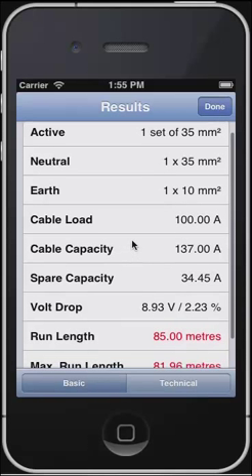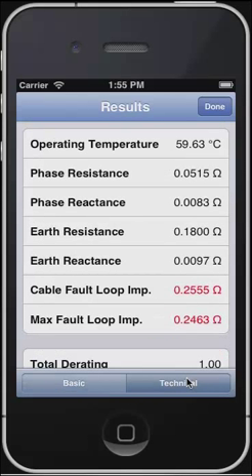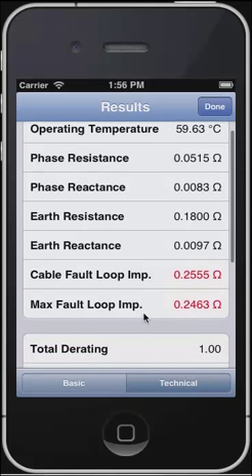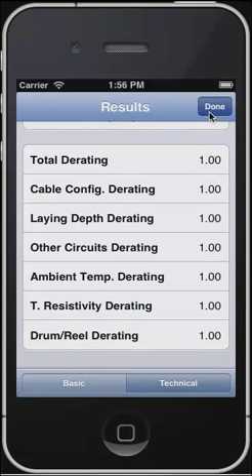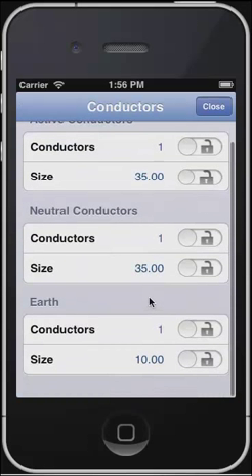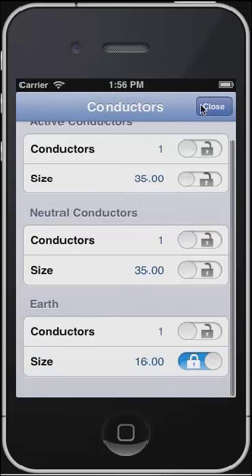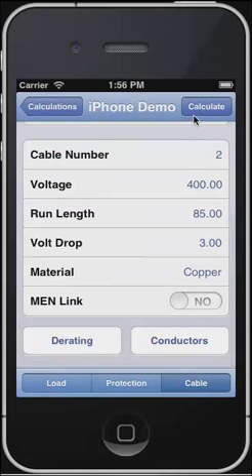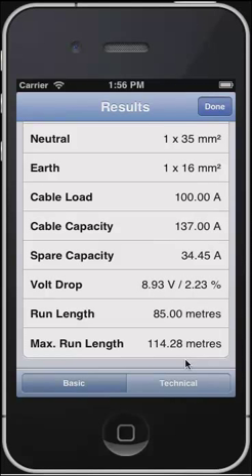As you can see, the calculation shows the size of the cable, the earth, the load, and so on. We can see in red that we have a warning — all warnings will be displayed in red. That warning is an earth fault loop problem. We can address this by putting on an RCD or ticking MEN link, or we can go to the conductors and specify a 16mm earth. After closing and redoing the calculation, we can see that the earth fault loop error has now been corrected.